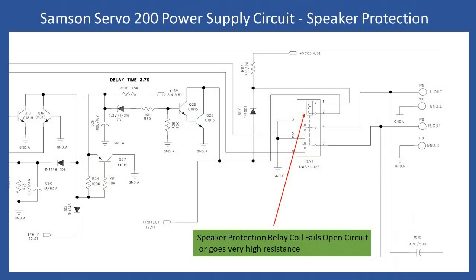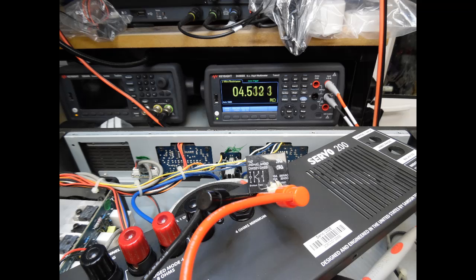The most common cause is that the relay coil goes open circuit, so the relay cannot change over, meaning there's no connection to the speakers. Or if it doesn't go fully open circuit, the resistance goes up into the order of megohms—in this case it went up to about 4+ megohms.